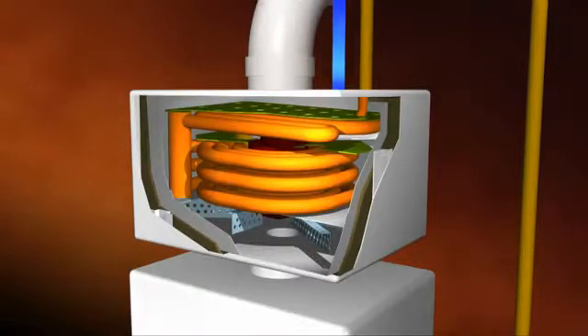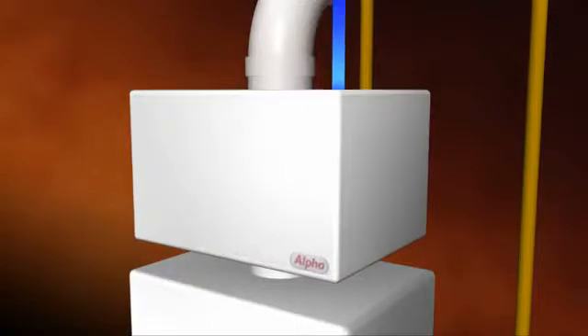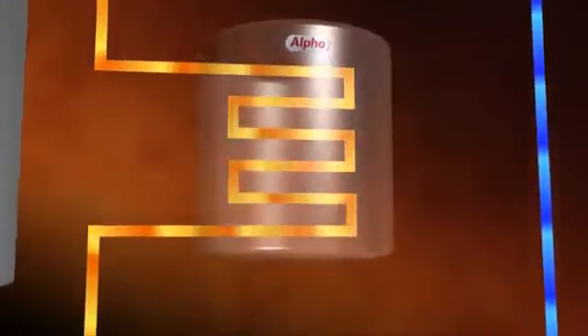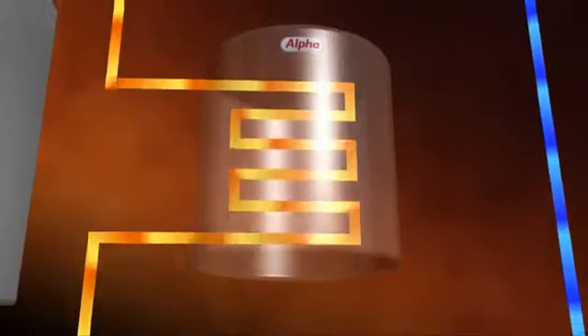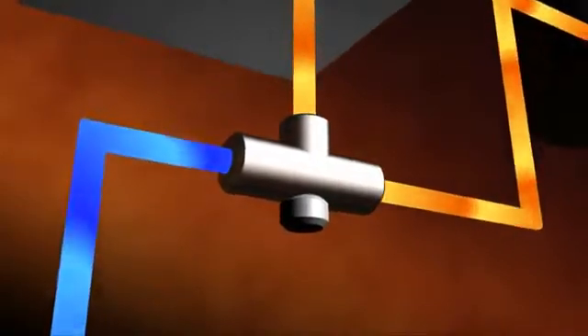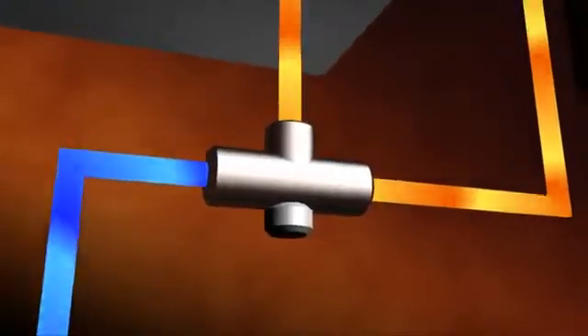The flue gases pass through the middle of the Alpha gas saver. The warmed water then passes through the FlowSmart thermal store where it picks up even more heat. When the thermal store is at its hottest, the mains water leaves the FlowSmart at a much higher temperature than is required. So it is mixed with incoming cold water from the mains through a blending valve.